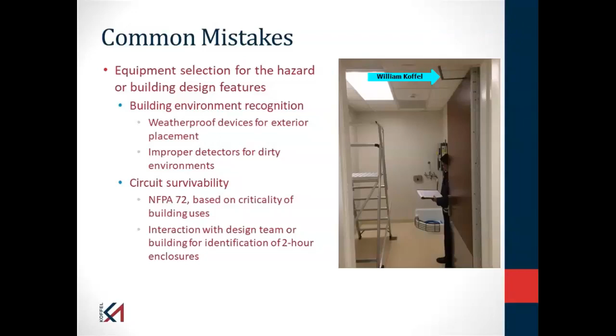This particular facility, not solely from this scenario, they were experiencing on the magnitude of 30 nuisance alarms a month. A lot of it had to do with improper selection of equipment or improper programming of the equipment that caused alarm conditions when it didn't really need to. So, again, you as the owner, you know your building better than any of us, might want to weigh in on whether this equipment is proper for that application.